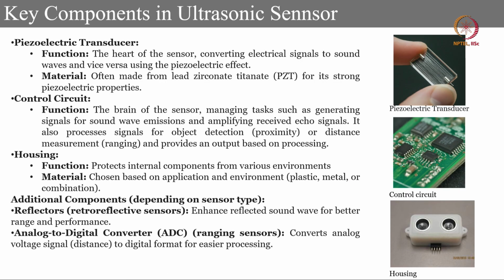So, piezoelectric transducers, we have functional and material. The function is the heart of the sensor, converting electrical signal to waves and vice versa. This is your piezoelectric material. That is why we say that a piezoelectric transducer is the heart of this particular sensor. The material that is used is lead zirconate titanate. Lead zirconate titanate is one of the best materials for piezoelectricity. It is called PZT. However, people use different kinds of material to change the properties of the transducer.